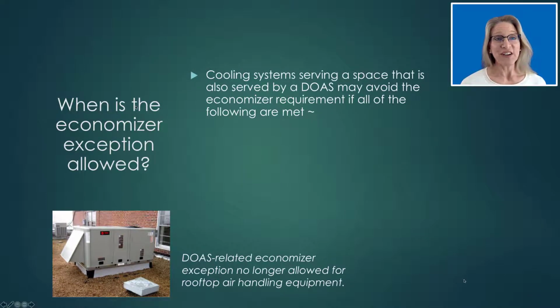So recall, there is an exception to economizer for areas and spaces that are served by a DOAS. Now, this exception is helpful as it allows higher efficiency cooling equipment that does not have the capability of having an economizer to not have to comply with the economizer provision, provided that the equipment or system is paired with a DOAS. So, for example, a common one is ductless heat pumps.